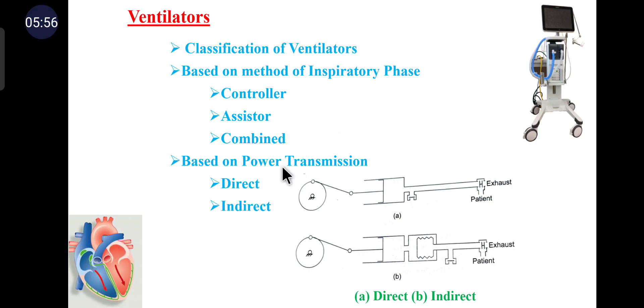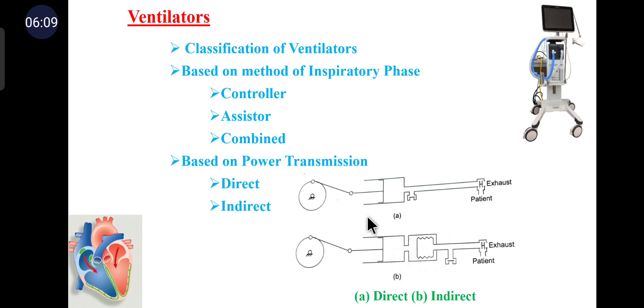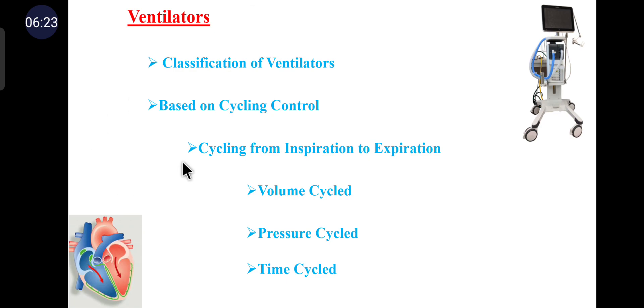Classification based on power transmission includes direct and indirect power transmission. Direct power means the ventilator delivers gas directly from the source or compressor to the patient. Indirect power means the ventilator has separate patient and power systems, where the pressure in the power system determines the flow rate.